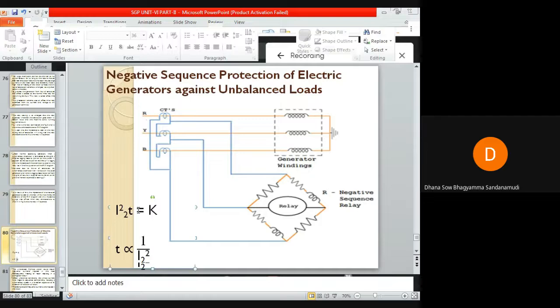I2 is the negative sequence component current, and K is the constant proportional to the thermal capacity of the generator rotor. Any equipment will have a maximum temperature resisting capacity. If that capacity is exceeded beyond its range, then it will affect the operation of that particular part of the machine or the machine itself. So this is about negative sequence protection of the electric generator under unbalanced load.